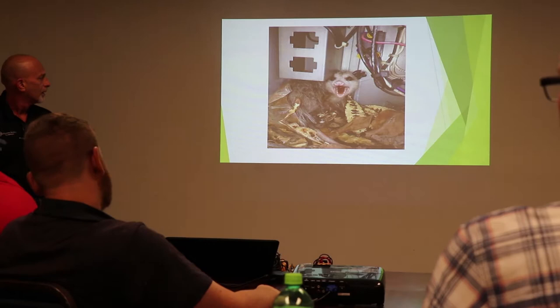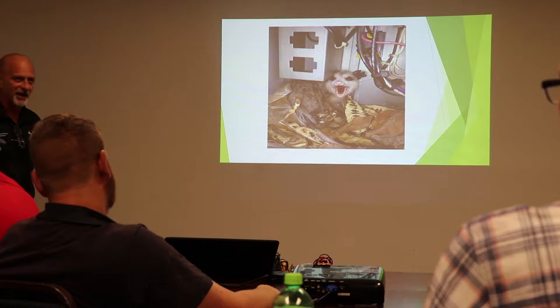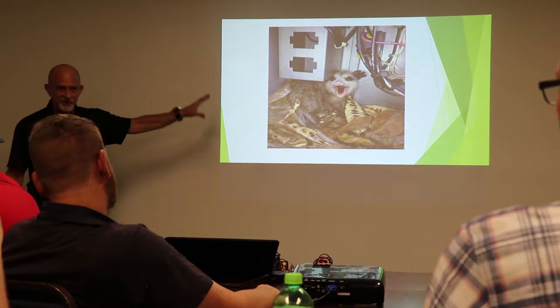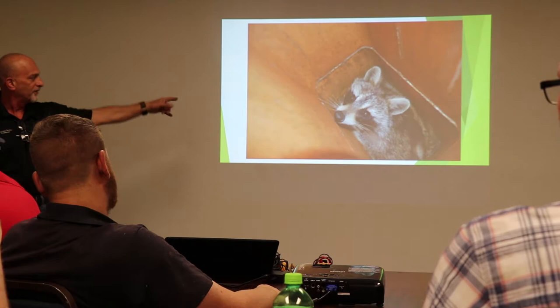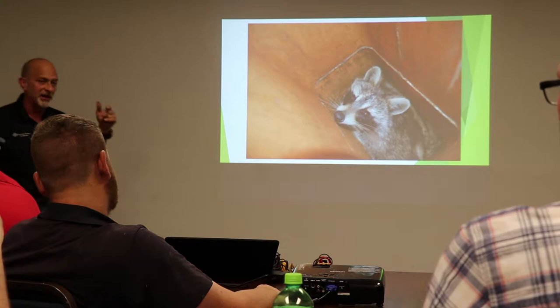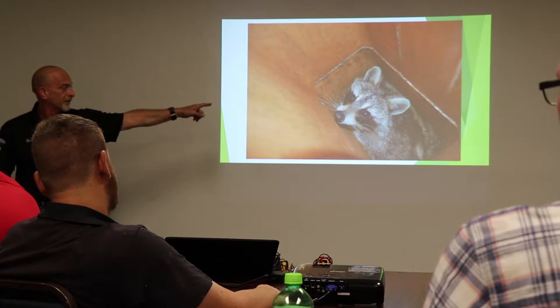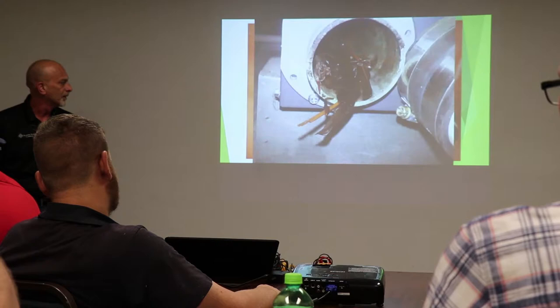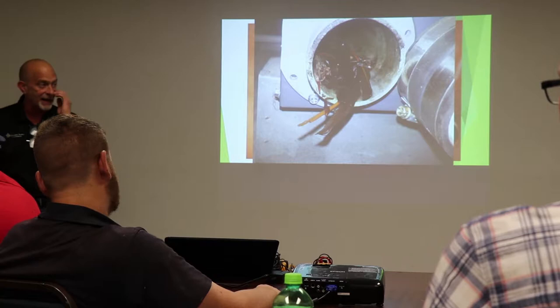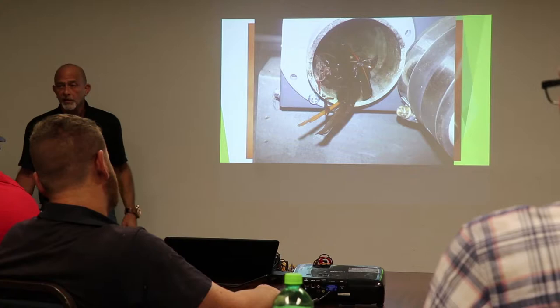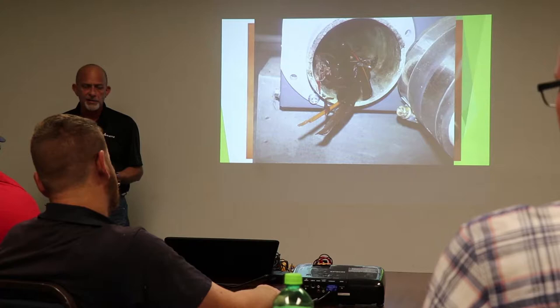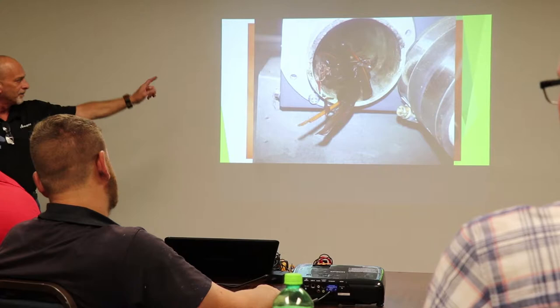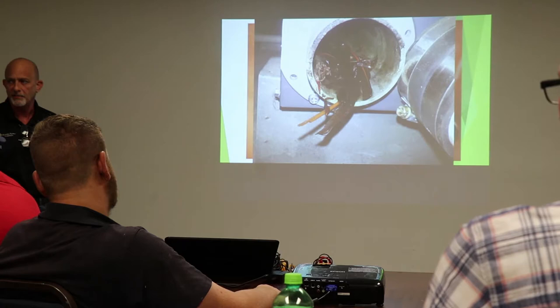Careful pulling stuff apart if it's been sitting a while. You may find critters in there. I just put this one in for laughs. Believe me, guys, this isn't a doctored photo. You may find critters living in equipment. Remember I talked about inspecting vent pipes and everything else. Well, if we got an 80% furnace, we're going up a clay or a brick chimney, right? You may have Rocky sitting in there. They got in there, fell in there, couldn't get out. Definitely see a lot of that, both in 80% furnaces and 90-plus furnaces. That's a 90-plus that made it all the way back to the furnace. Usually back to the furnace, you'll get mice because they're smaller. A lot of bugs, butterflies. I've seen just about everything. On occasion, I've had a few birds all the way up to a furnace on a 90-plus, but a lot on an 80%er. But usually on the 80%er, they're right on top of the inducer. When you fire it up, you hear the beep hitting that.